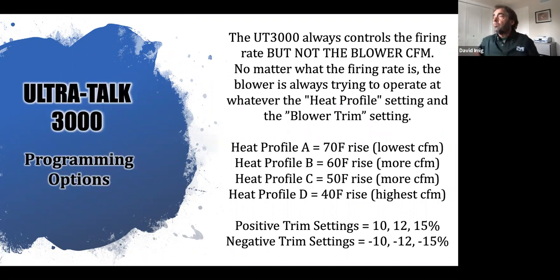We do not control the blower. Those questions are asked all the time. Why can't you control our blower so that we don't need to use bypass, or that we can slow it down based on the zone or number of zones calling? Equipment manufacturers are never going to let us control minimums on a blower. They're not going to allow you to possibly set up a train wreck and cause warranty issues.